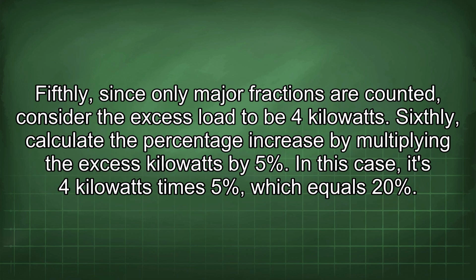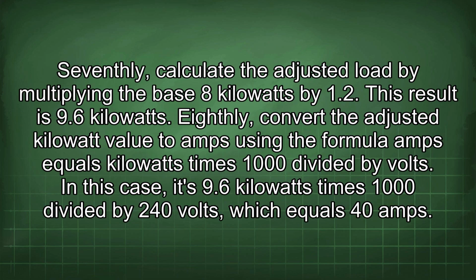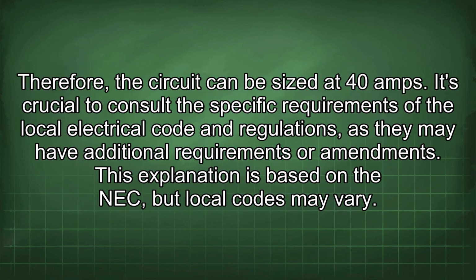Fifthly, since only major fractions are counted, consider the excess load to be 4 kilowatts. Sixthly, calculate the percentage increase by multiplying the excess kilowatts by 5%. In this case, it's 4 kilowatts times 5%, which equals 20%. Seventhly, calculate the adjusted load by multiplying the base 8 kilowatts by 1.2. This result is 9.6 kilowatts. Eighthly, convert the adjusted kilowatt value to amps using the formula amps equals kilowatts times 1000 divided by volts. In this case, it's 9.6 kilowatts times 1000 divided by 240 volts, which equals 40 amps. Therefore, the circuit can be sized at 40 amps.